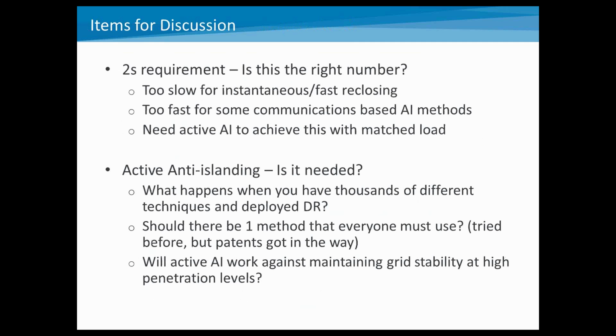So a couple items for the discussion. I just wanted to throw these out, and I'm sure we'll have some discussion here in a second, but some comments on this. Obviously, there's a two-second requirement in 1547 right now, and the question is, is this the right number? Some things to think about. It's too slow for instantaneous reclosing. So if we have on the distribution system utilities using instantaneous or super fast reclosing circuitry, that happens within 2 seconds. And so it's not going to be coordinated with that anyway.